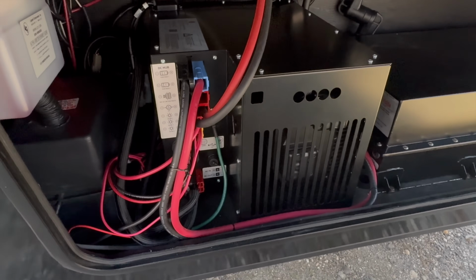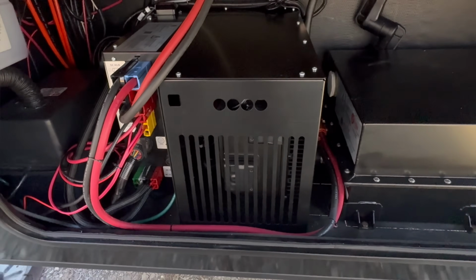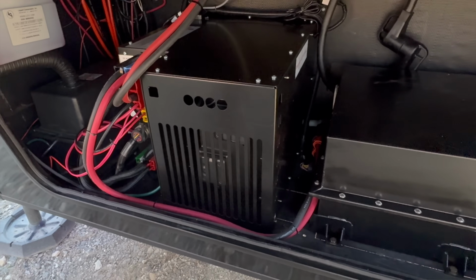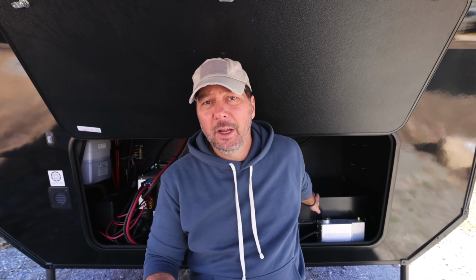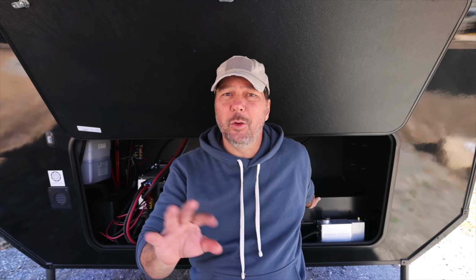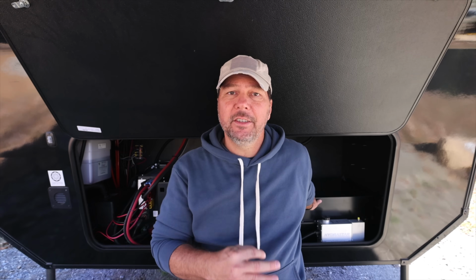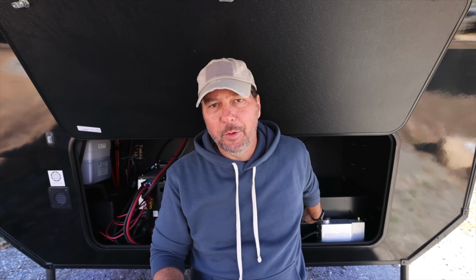But the inverter inside this PDH is a little bit special. Number one, it's designed to work with this higher voltage, 57 volts, 51 nominal, coming from this system, so it can take advantage of higher power over smaller lines using higher voltage and lower amperage from this battery system.